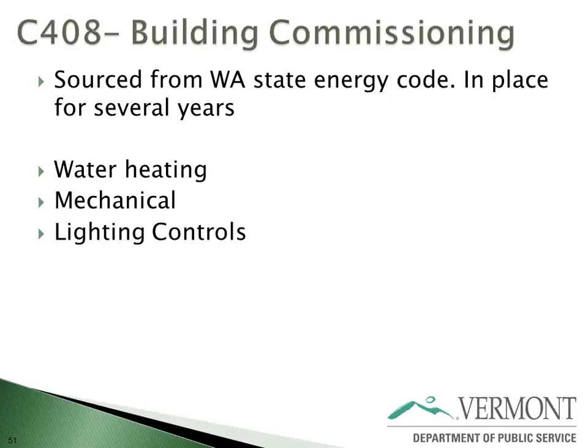So in Vermont's code, there's a criteria for buildings of 50,000 square feet or more, which gets very specific functional testing on economizers, hydronic systems, and VAV fan control—systems already required by code. So it's essentially: let's just commission those, make sure they're being tested, and call that good. It's only for big buildings where there really should be commissioning anyway, since they're likely doing it already.